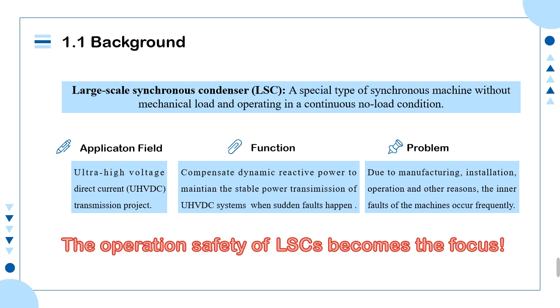Large-scale synchronous condenser (LSC) is a special type of synchronous machine without mechanical load and operating in a continuous no-load condition. LSCs are selected as a main dynamic reactive power compensation device for ultra-high voltage direct current transmission projects. Owing to the variable operation of the system, the possibility of inner faults for the machine is relatively high. To maintain the stable power transmission, the operation safety of LSC should be focused.